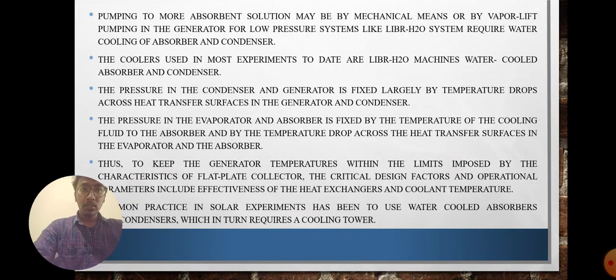Pumping of the absorbent solution may be by mechanical means or by vapor lift pumping in the generator for low pressure systems. Systems like the LiBr-H2O system require water cooling of the absorber and condenser. The coolers used in most experiments to date are LiBr-H2O machines, lithium bromide water machines, with water cooled absorber and condenser. The pressure in the condenser and generator is fixed largely by temperature drops across the heat transfer surfaces in the generator and condenser. The pressure in the evaporator and absorber is fixed by the temperature of the cooling fluid to the absorber and then by the temperature drops across the heat transfer surfaces in the evaporator and the absorber.